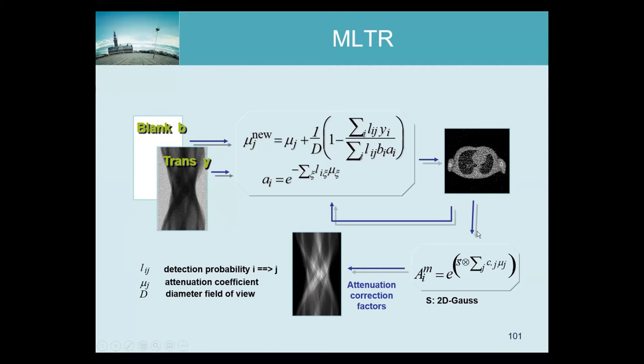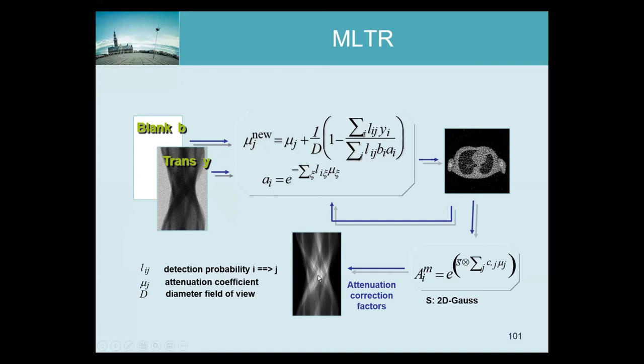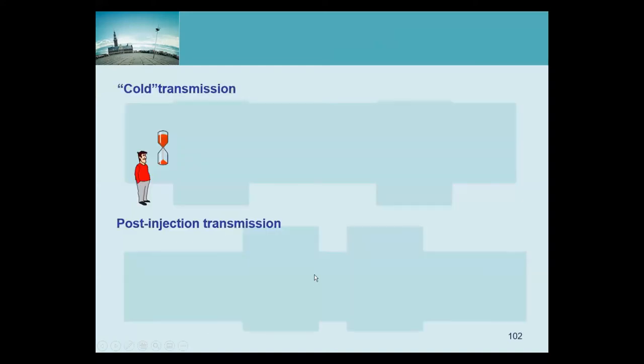If the reconstructed image is to be used only for attenuation correction, it's actually a good idea to iterate quite long and not worry too much about the noise, because that noise is highly negatively correlated. When you compute line integrals through those images, a lot of the noise will cancel. Even if the image looks horrible, if you forward project it, you get a pretty good sinogram that is far less noisy than the original one. You can also do a little bit of smoothing, then compute the exponent, and get the attenuation correction sinogram.